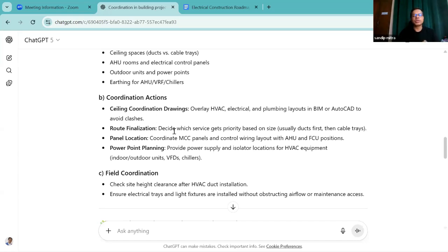For route finalization, decide which service gets priority based on size - usually duct first, then cable tray, then pipes - though this may vary based on the project. For panel locations, coordinate the MCC panel and control wiring layout with AHU and FCU positions.